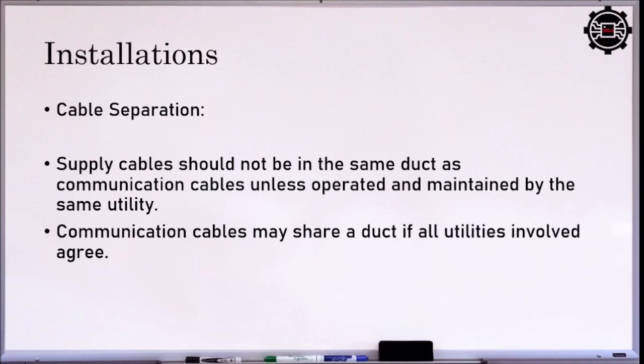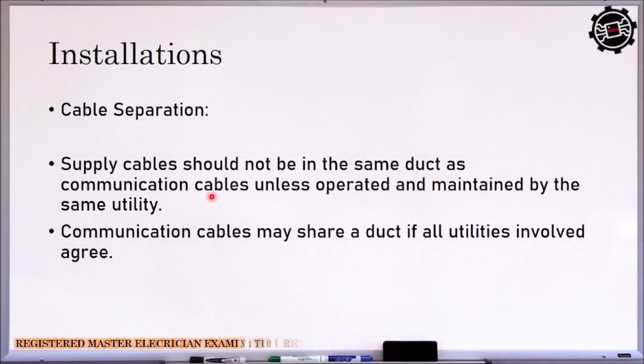Okay. So installation, so if you have cable separation, so supply cable should not be in the same duct as communication cable unless operated and maintained by the same utility. So same pa rin kanina, no? As long as they are of different utility or different companies. So, hindi pwedeng magkasama yung supply cable at communication cable. Pero if isa lang, pwede lang. Communication cable may share a duct if the utilities involved agree. No? Sa the exception also, if yung dalawang company ay may agreement, so pwede silang magkasabay sa isang ducting or sa isang daanan.